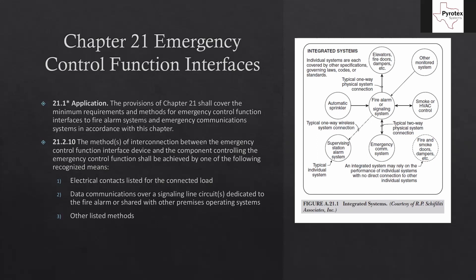If we look at the diagram on the right, we can see a pictograph of how the fire alarm is going to talk to all these other things. The fire alarm is in the center. Down at the six o'clock position there's an emergency communication system with a typical two-way physical system connection, because if your building has an ECS system it's most likely part of the fire alarm. On the right-hand side you see the smoke or HVAC control — that's kind of a two-way communication. We get the supervisory signal from the duct and tell that system to shut down. Most of the time it's two-way: we're sending a shutdown signal after we receive an alarm or supervisory signal from them.